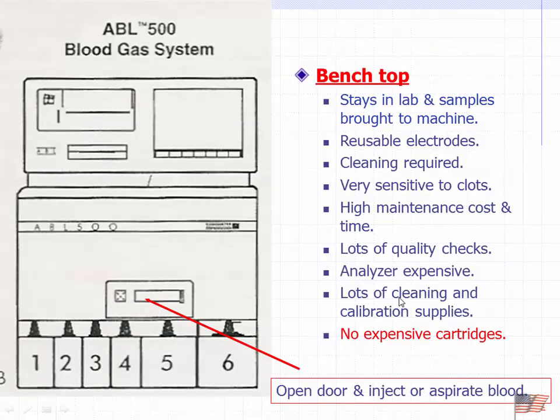All right, so this is an example of a benchtop unit where we would end up having a little access panel door that would open up and we'd be able to insert our sample. Again, as the name implies, it sits in the lab at all points in time. The key part I want you to remember about this one is that it has reusable electrodes. So the pH electrode, the PCO2 electrode, and the PO2 electrode are semi-permanent items that we would do maintenance on as far as cleaning them and doing remembraning and stuff like that.